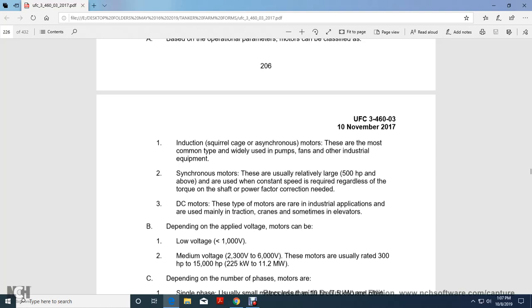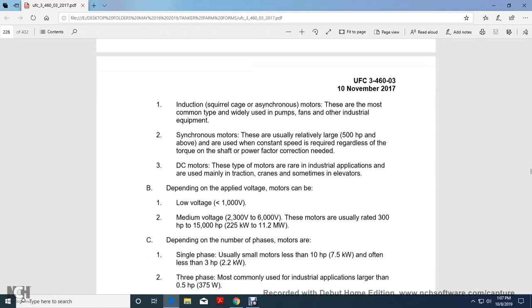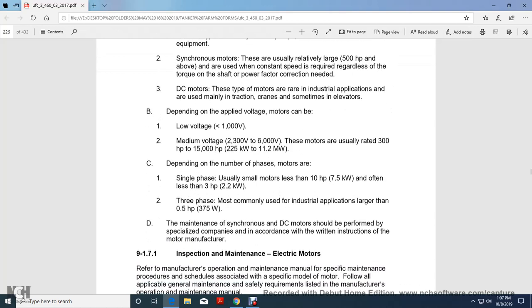asynchronous motors, the most common type, widely used in pumps and fan industrial equipment. Synchronous motors are usually relatively large, 500 horsepower and above, usually with a constant speed required regardless of the torque of the shaft or the power factor needed. DC motors are a rare type in industrial application, used mainly in traction and cranes and sometimes in elevators. Depending on applied voltage, motors can be low voltage, less than 1,000 volts, or medium voltage, 2,300 to 6,000 volts. These motors are rated from 300 horsepower to 15,000 horsepower.